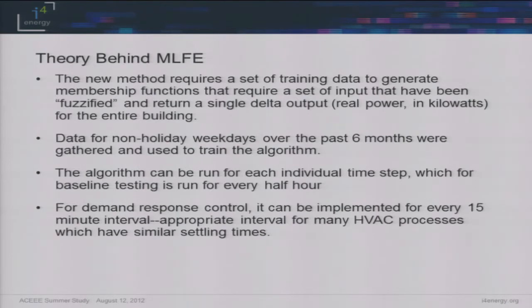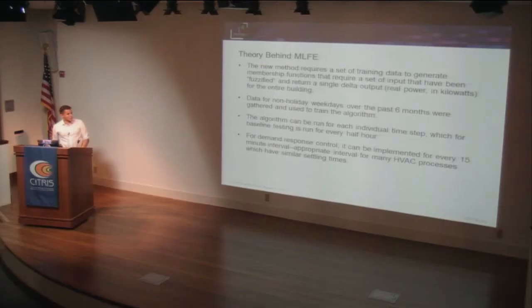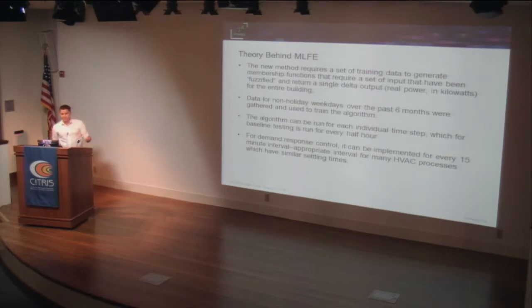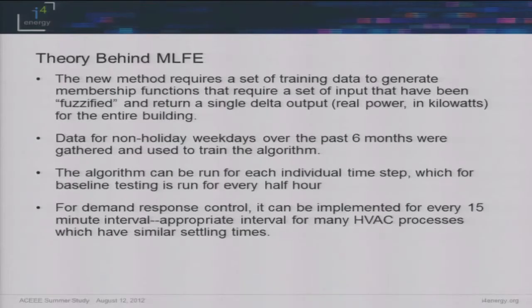We ran the model for each individual time step — in our case 30-minute time steps for an entire day from 12 o'clock to 5:30, basically doing a test for every half hour. We can change this to five-minute or 15-minute intervals if we have the data. Generally, we feel like a lot of the systems in the building have settling times greater than five minutes, so 15-minute intervals for thermal systems is a pretty good target, and the computational time is very minimal.